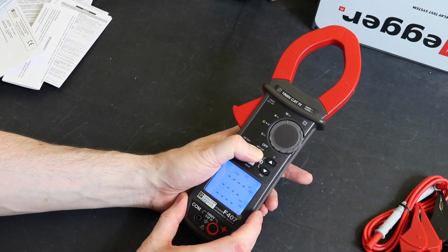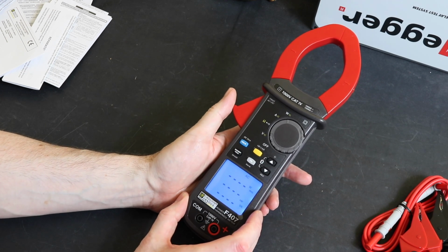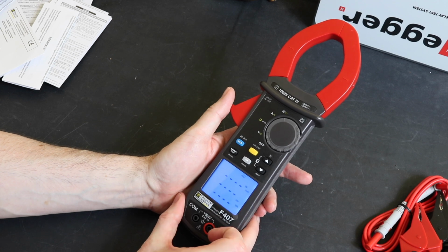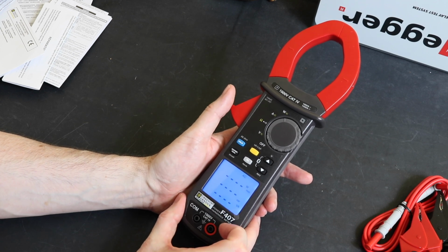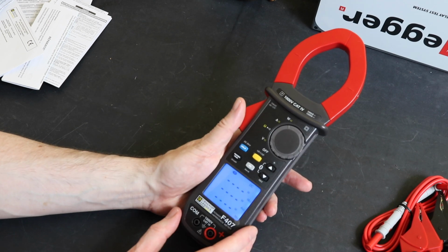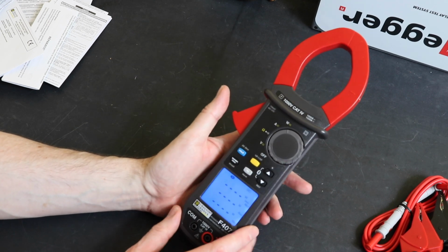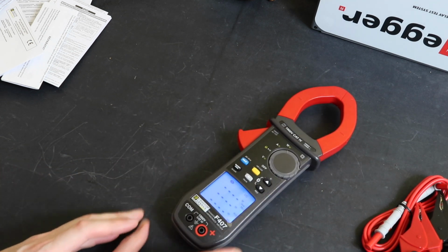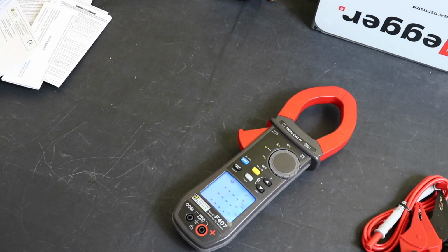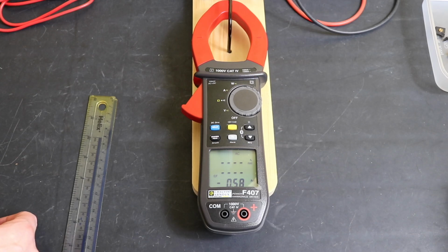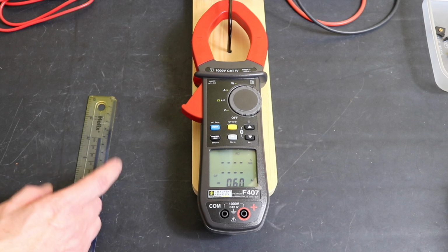You have to hold it down to switch between single phase and 3 phase, and we get our watts, VAR and our VA on the actual display there. So that's our main functionality of the meter there. We'll set up with our SMRT again, and we'll make some measurements on it and see how well we get on with it. We are set up on a single turn clamp table.